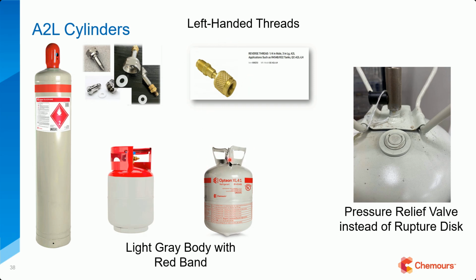Because you're putting an A2L refrigerant in a system that's not designed for it. So you do not want to put 454B in an existing R410A system, or anything with 454A or C in an existing system like 404A.